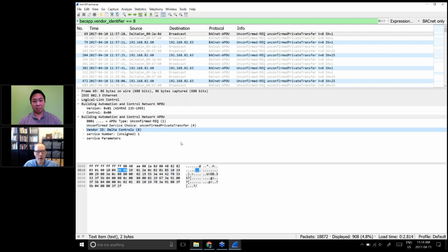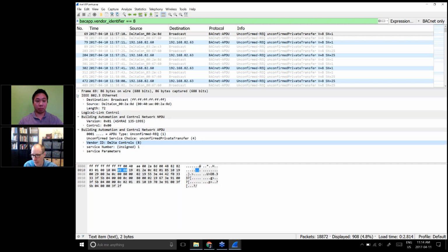So the point of all of this explanation is that almost anything inside the packet, from the IP address, the MAC address, stuff in BACnet in the NPDU, like the DNet, the SNet, DADDR, SADDR, can all be used as filterable criteria, plus all the APDU components that Ping was just displaying there, so that we can look for a needle in a haystack a lot more effectively.